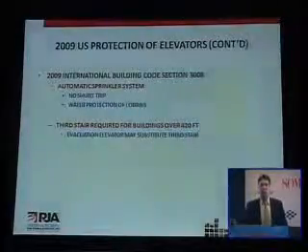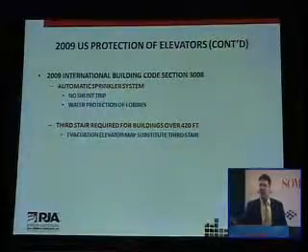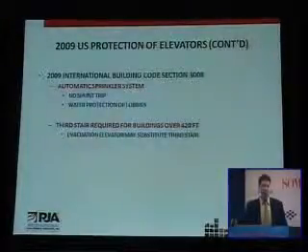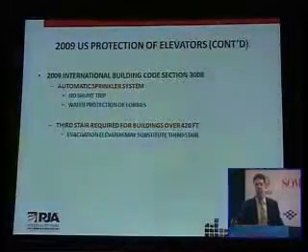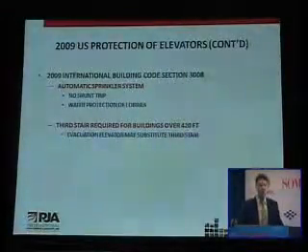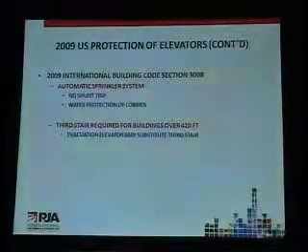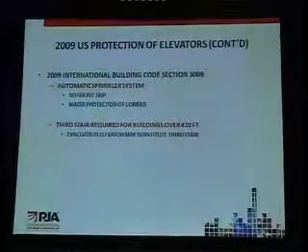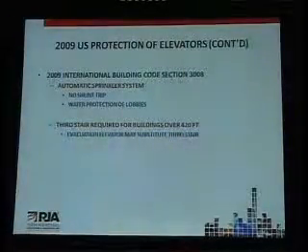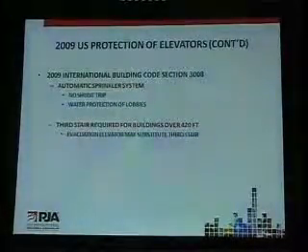Now, you're thinking, why would anybody ever want to do this strategy? We've designed super tall buildings in the past, and they've worked, and we've done it. However, the International Building Code 2009 edition has a number of other enhanced requirements other than just elevator evacuation. One of them, and probably the most painful for architects, developers, and building owners, is when you start reducing their leasable floor area. One of the big items is any building that's now over 420 feet or 126 meters is now required to have a third dedicated stair for firefighter access.